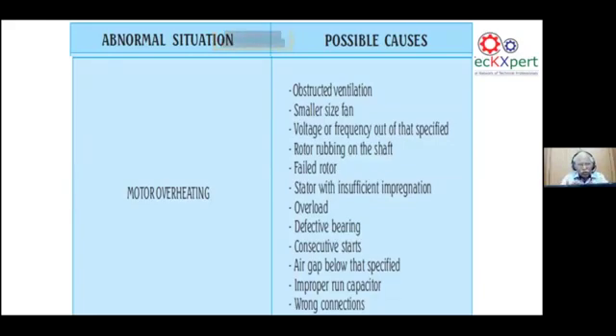Then all the motor related problems like rotor rubbing on the shaft, a failed rotor, or a stator with insufficient impregnation, these are all coming from the OEM side, and what is to be maintained as per the design and what is maintained. On the field load side, overloading is also a cause of overheating, and so is a defective bearing. Having gone for a VFD on an existing IE1 motor, which is a standard or conventional motor, definitely the bearing needs to be changed to an insulated type bearing. If we have not changed it, the bearing is definitely the first culprit to fail. That is going to fail first, and it will have an impact on the motor's running temperature also. It goes up by 5 to 10 degrees and more also.